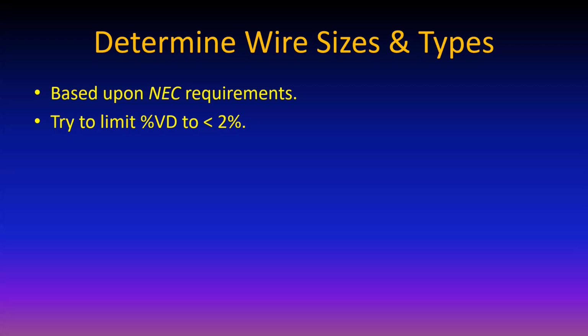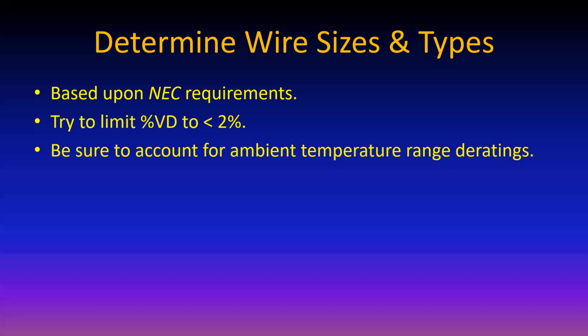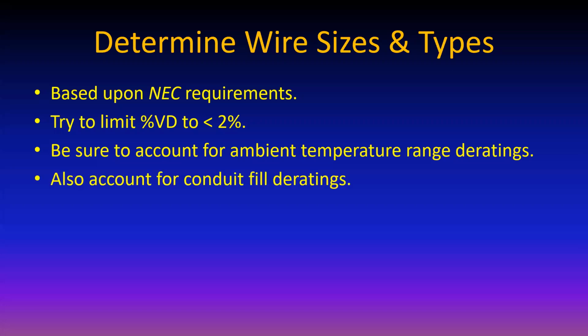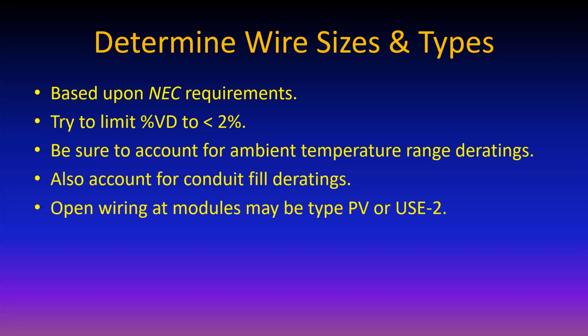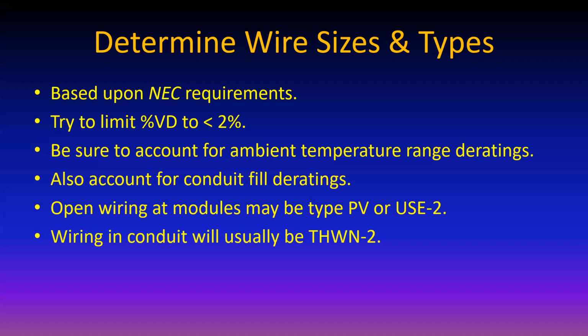But if you're in a bigger commercial, then you need to pay some attention to voltage drop and the length of wire and whether you need to make it a little bigger. Need to do all your derating, ambient temperature. You need to do conduit fill deratings, and they're all specified very clearly in the National Electrical Code. Open wiring at the modules is PV or USE-2, we already mentioned that. Conduit is usually THWN-2, that's resistant to all kinds of stuff, plus it's 90-degree wire.